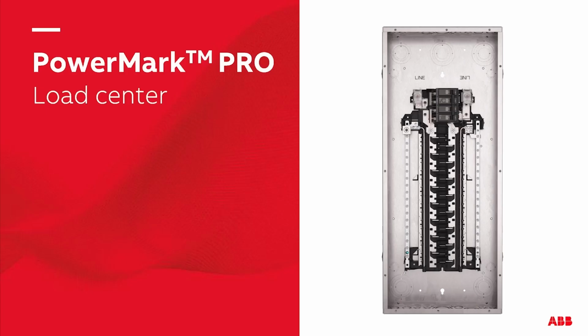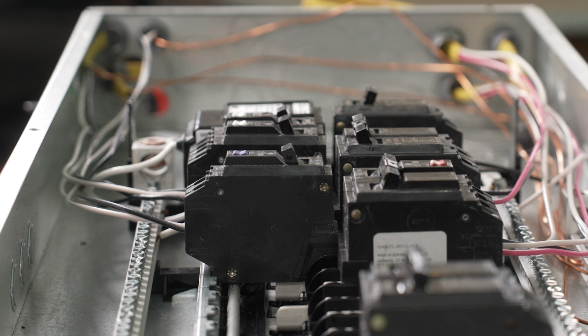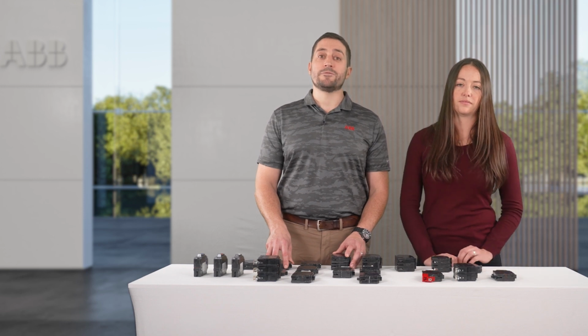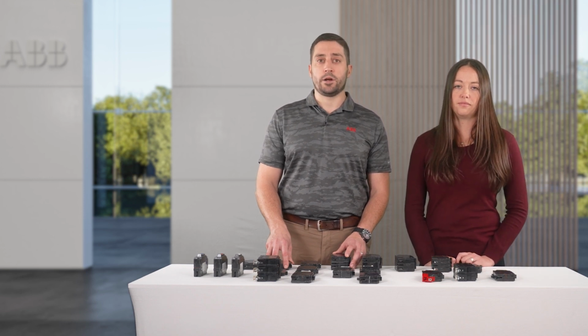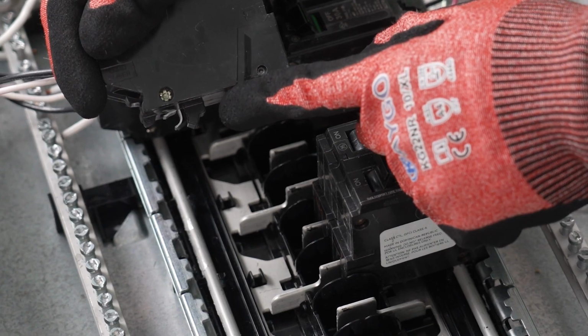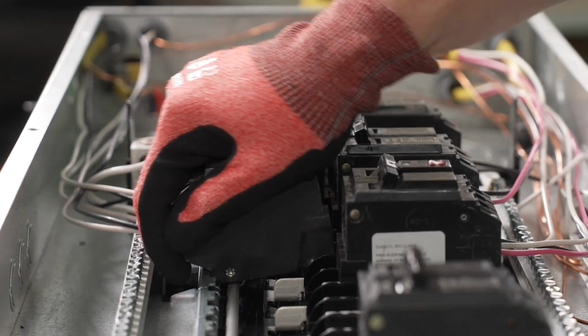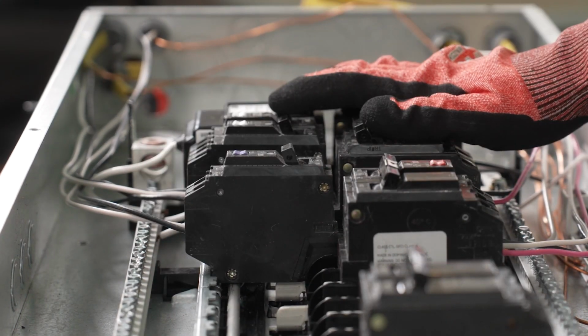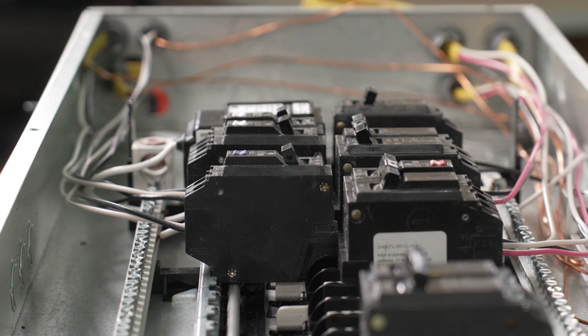We have multiple breaker installation options available. Our PowerMark Pro load centers accept the plug-on neutral connection system known as ReliaLock. It incorporates a clip-on breaker and a rounded neutral mounting bar on the load center's interior. It is rounded to facilitate mounting the breakers from many different angles and is tied into the traditional neutral bar. Installation of these breakers is very similar to that of a traditional breaker. The heel of the breaker is slid into the metal mounting rail. Then, while rotating the breaker into place, the ReliaLock clip securely interlocks with the ReliaLock bar.